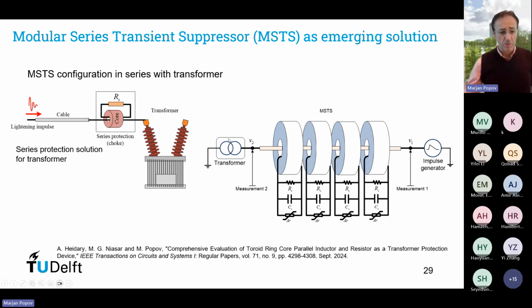The recent work on this has been published this month, as you can see, in IEEE Transactions on Circuits and Systems. We developed a modular series transient suppressor. This is a device which is connected in series to the cable. Quite some numerical analysis and simulations have been conducted to find out how to adjust these parameters to be capable of suppressing particular transients with resonance frequencies. I will just show a few results, and again I refer the reader to the paper. This work is still ongoing, and we are still making plans to perform field measurements to see how this will operate in practice.